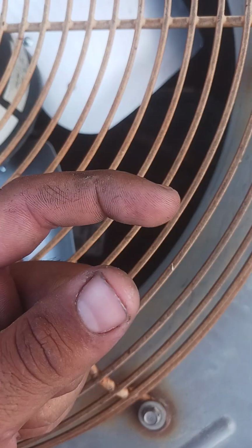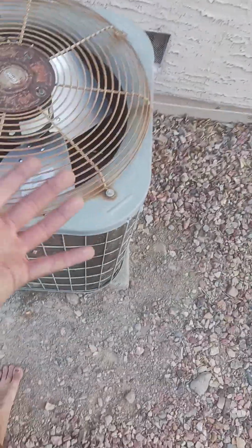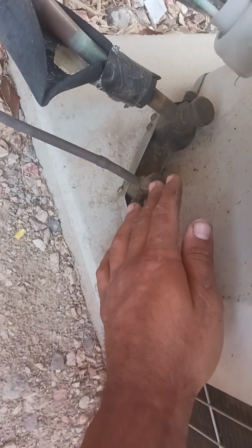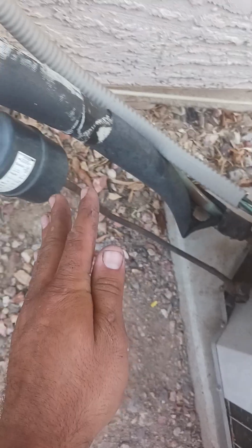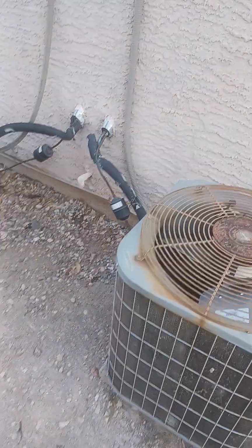A line comes out of it with hot gas, and it goes straight into this, and this fan on top pulls air from the side and pushes it out the top to remove the heat within the pipe to then try to condense that into a liquid. Once that's done, it comes straight out of the condenser basically into this line, what you call the liquid line. Okay, so that's the liquid line. And where does that go? That goes straight into your house. It goes up the wall.